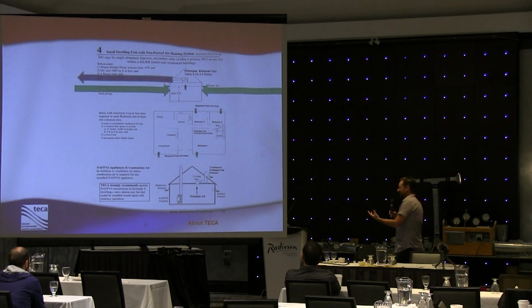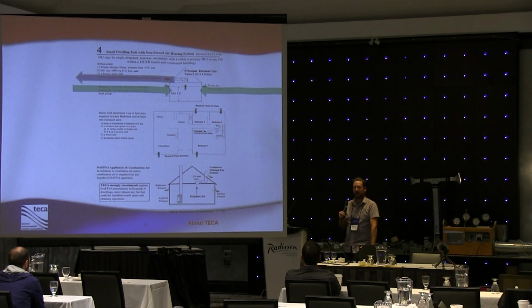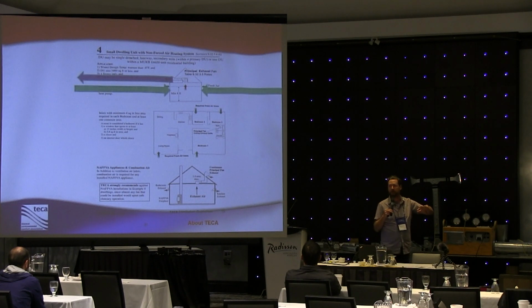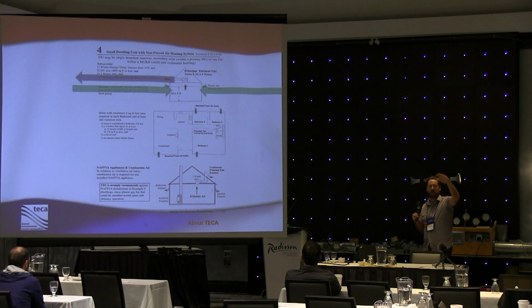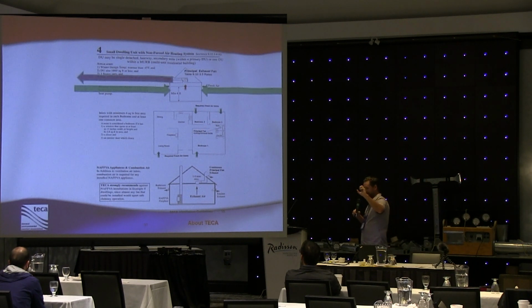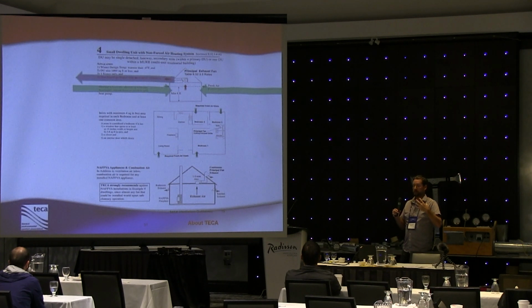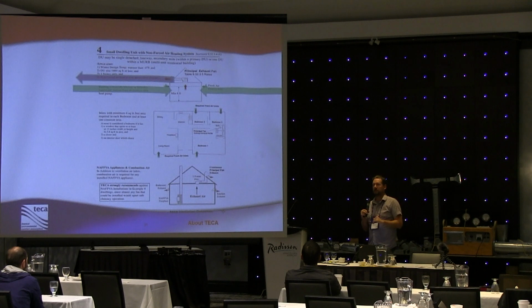You can imagine if we brought that fresh air in down at the baseboard level or at knee height, that cold air is going to create a cold air barrier. It's going to be very uncomfortable for the occupants. We want to make sure that we keep those at 6 feet off the floor. And I'm very particular about this type of system because I don't want that fresh air inlet to be installed somewhere that the occupant is going to be using that space. I would really hate to see it come directly into where someone has a desk perhaps or right over the headboard of their bed. We'll try to keep it kind of tucked away.